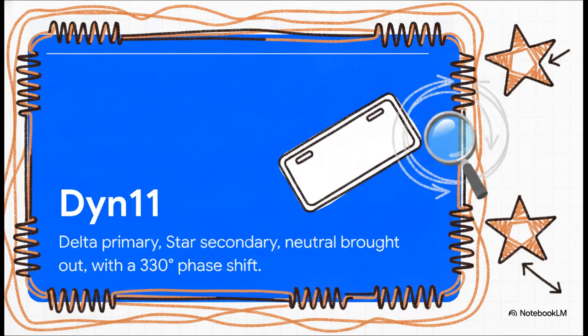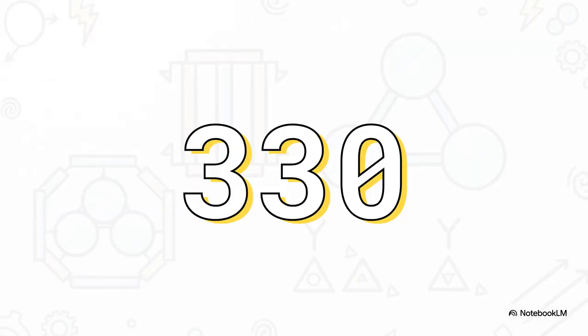Now, these crucial copper configurations aren't just hidden away inside the transformer tank. They're explicitly encoded into a compact little vector group license plate, something like Dyn11. So the trick here is knowing exactly how to read this code. The capital D tells us the primary winding is delta. The lowercase y means the secondary is star. And that little n signifies that the neutral point from the star secondary is physically brought out for us to use. And then, of course, there's that number at the end.